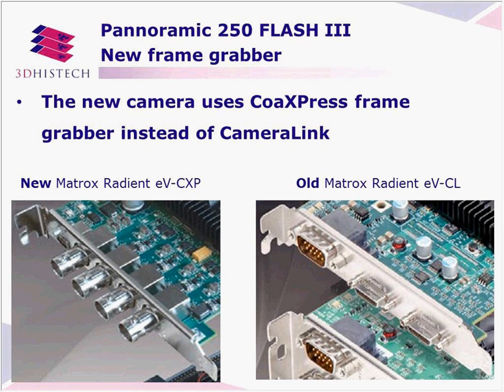It requires a new frame grabber, and this might be important in troubleshooting, installation, and service cases. The older camera was using Camera Link connection, and Camera Link is simply not capable of delivering the throughput speed necessary for this camera. The CoaXPress standard can deliver 25 gigabits per second, which is required to utilize the full capability of the camera.